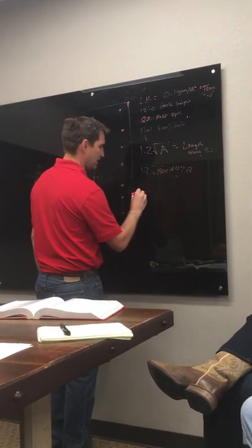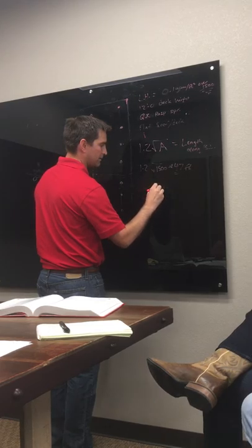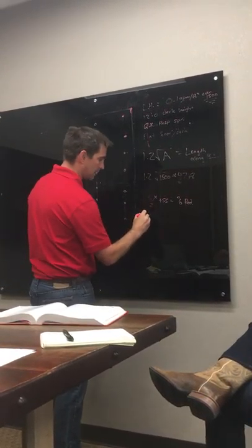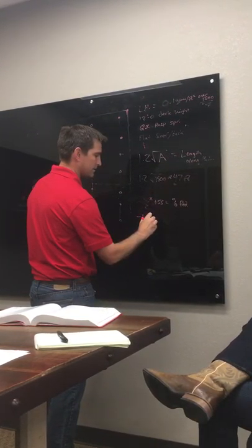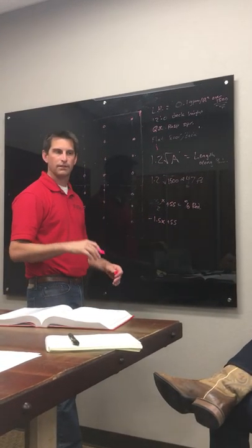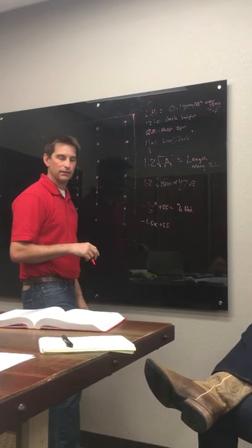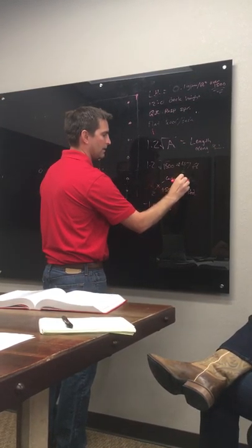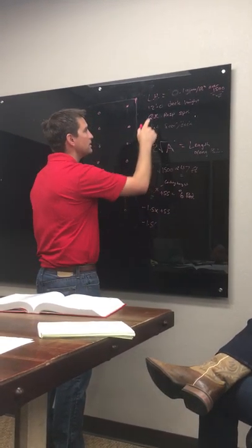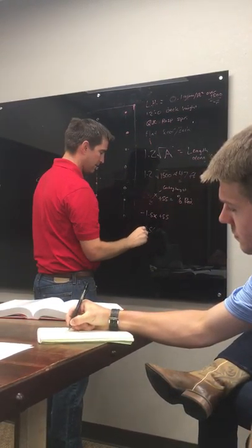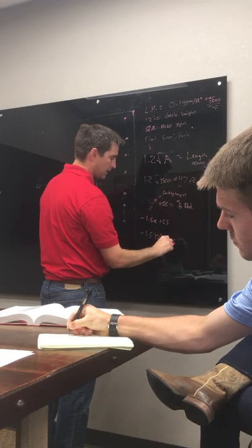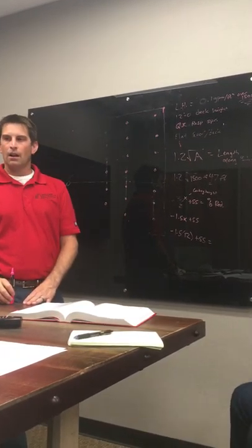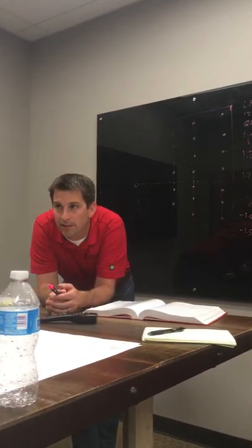Minus 3 halves times x plus 55 is my percent of reduction. When I punch it into my calculator, I just go negative 1.5 times x plus 55. It's a lot easier than trying to put in a fraction. X is your ceiling height. So negative 1.5 times 12, 12 foot, plus 55. Negative 1.5 times 12 is negative 18, so it's 37.